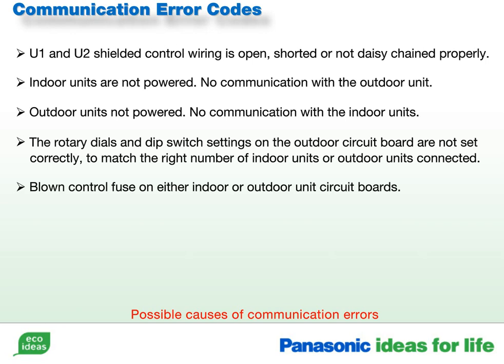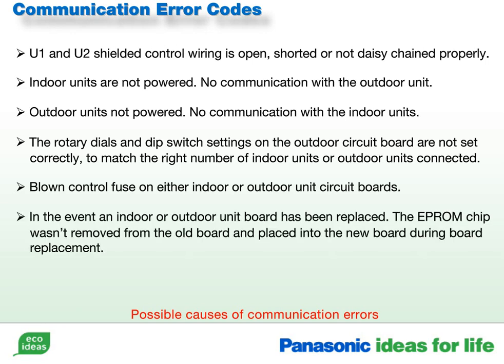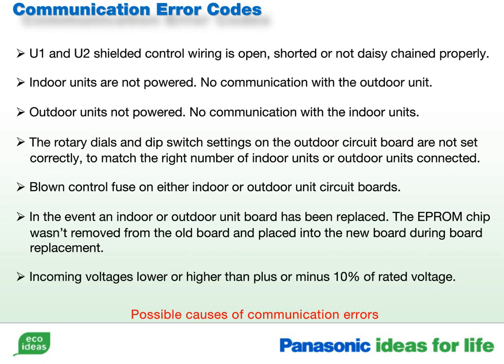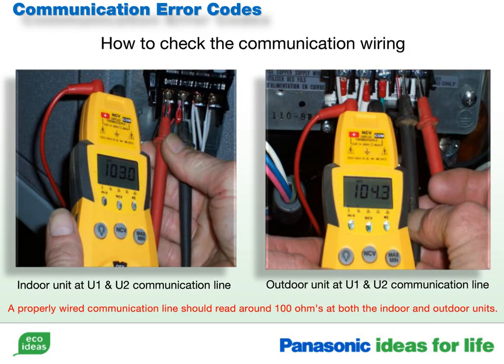A blown fuse on either the indoor or outdoor circuit board. An indoor or outdoor circuit board has been replaced and the EEPROM was not removed from the old board and transferred into the new board. Incoming voltages are lower or higher than 10% of the rated voltage. You can check your control wiring for a break or short by using a meter. Set your meter to the ohms scale, and measure the resistance at the U1 and U2 terminals. If your control wire has not been cut or grounded, you should read around 100 ohms at both the indoor and outdoor units.